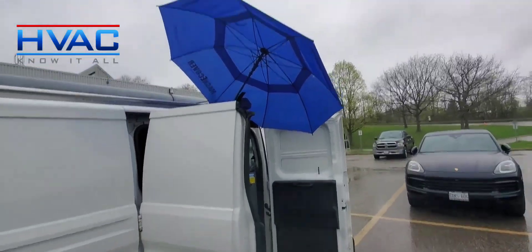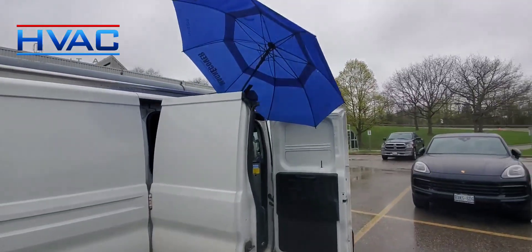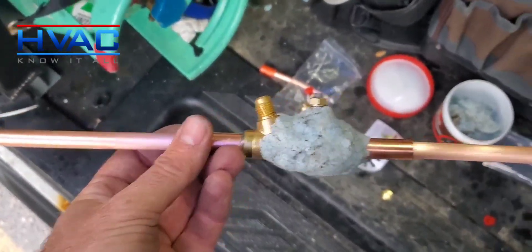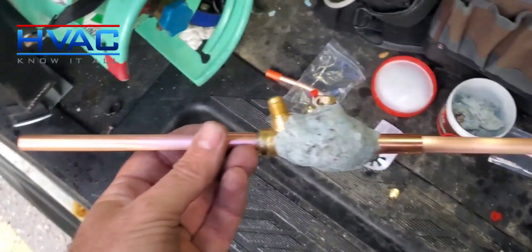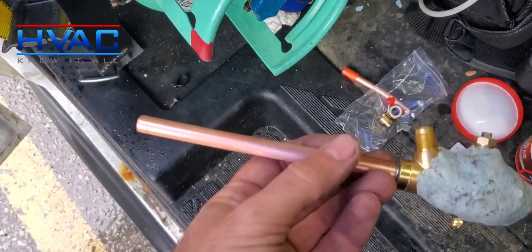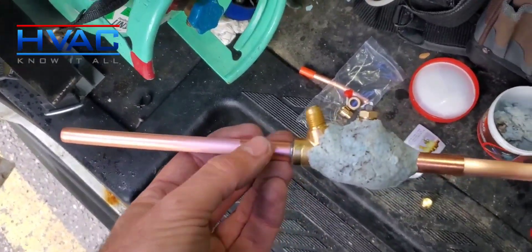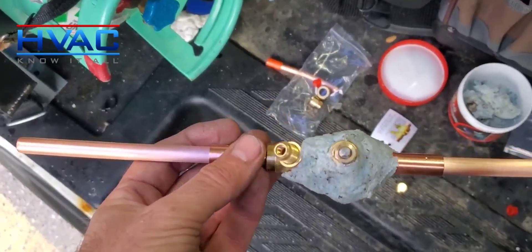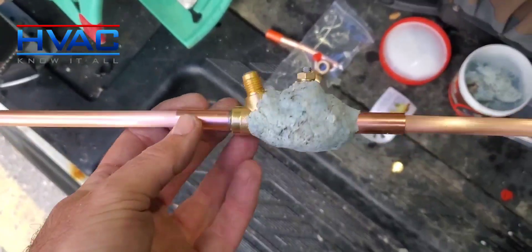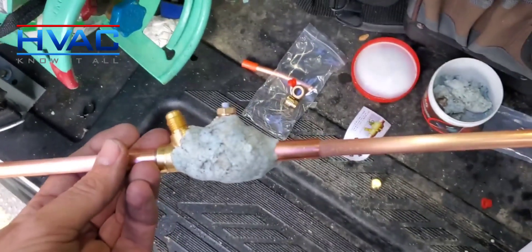I'm going to braze a piece out of my truck here and I've got the Supco umbrella up since I'm working outside because it's raining. I had to cut out a whole section of pipe. Somebody had used one of those pre-made flares you can buy at the supplier. It was leaking and it lost almost all of its charge because of that. I'm also cutting out this ball valve contraption because I don't know if they wrapped it when they brazed it, so I'm cutting the whole section out.